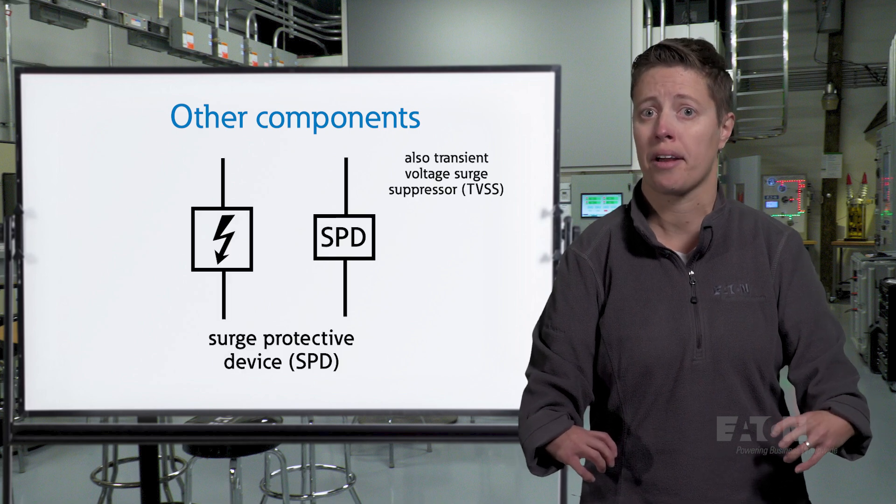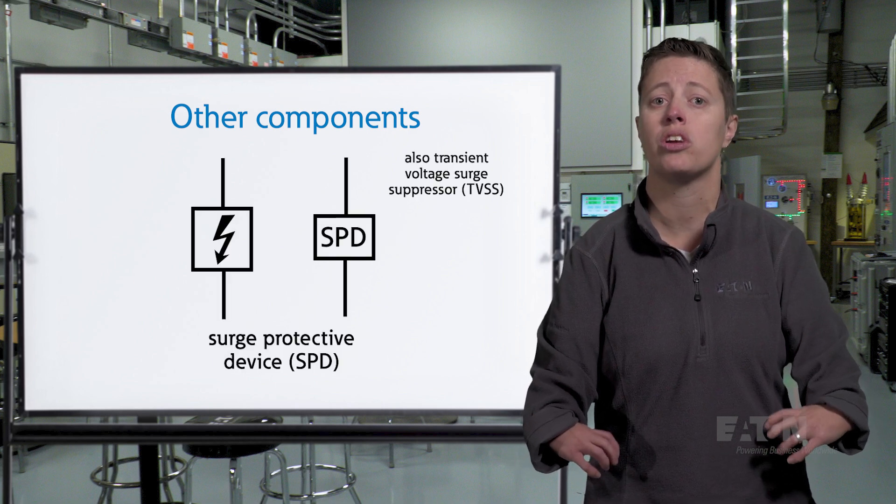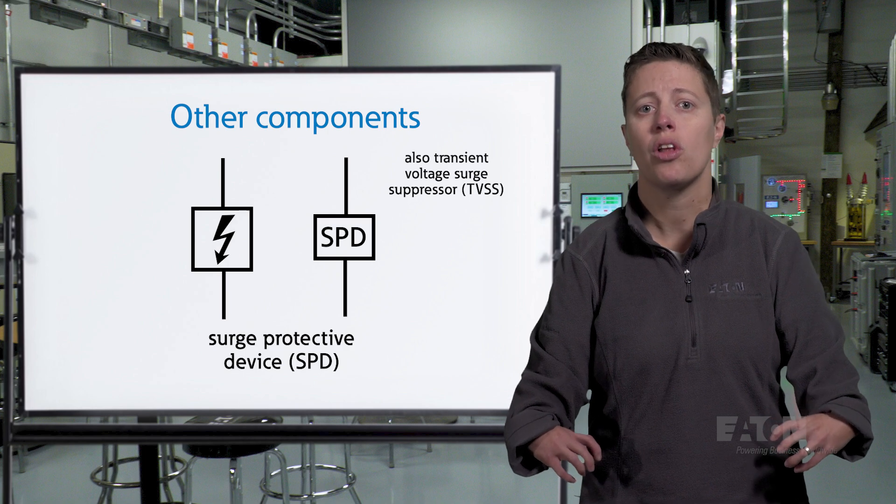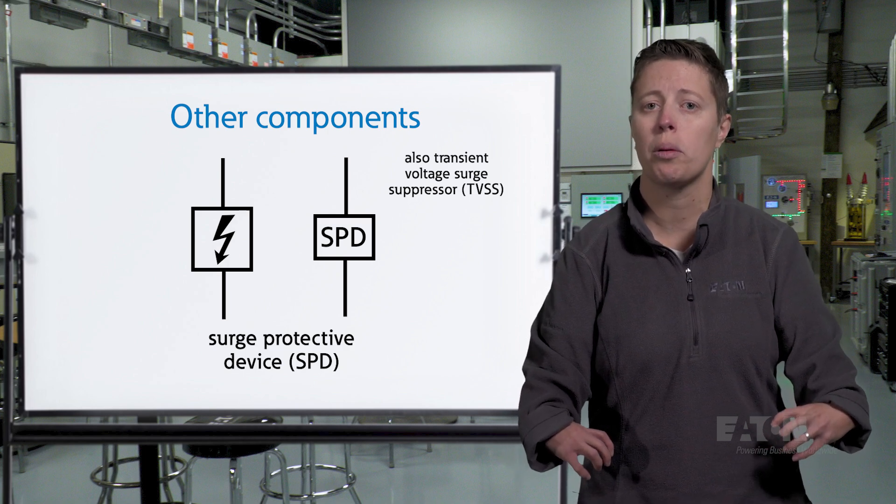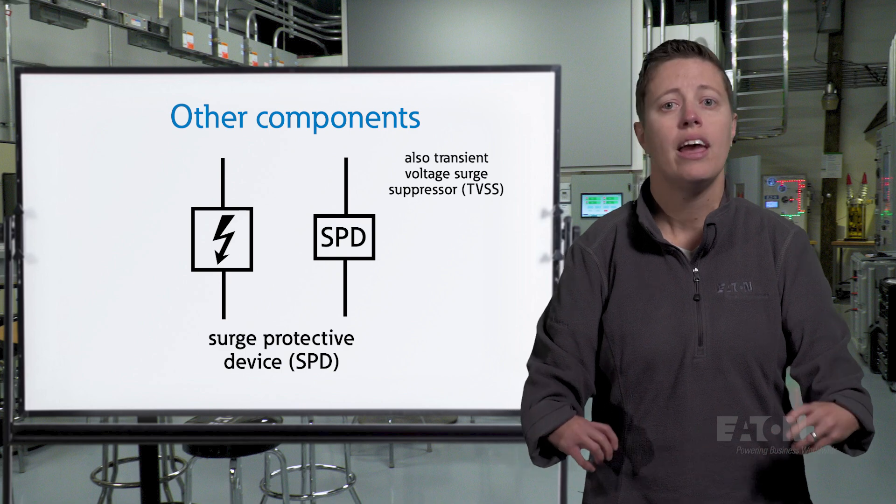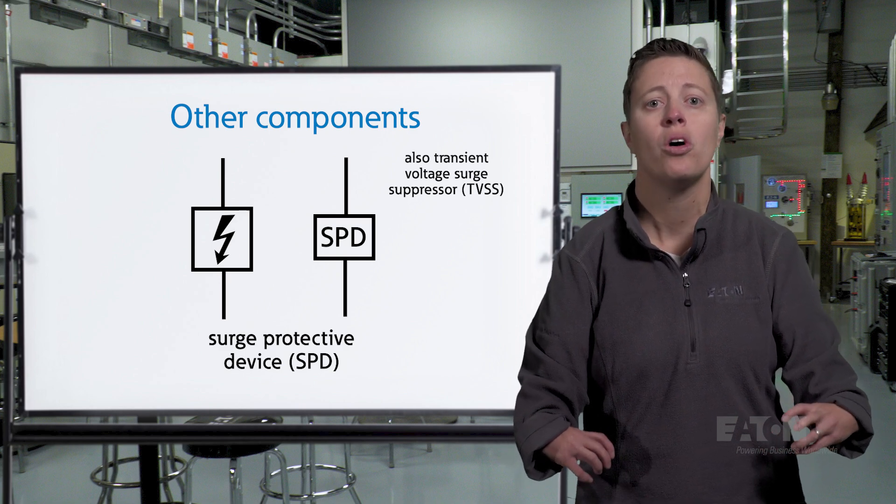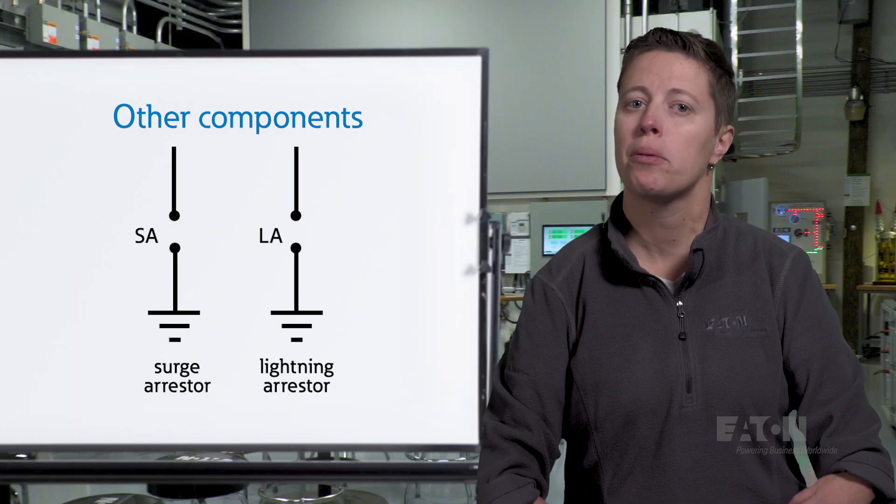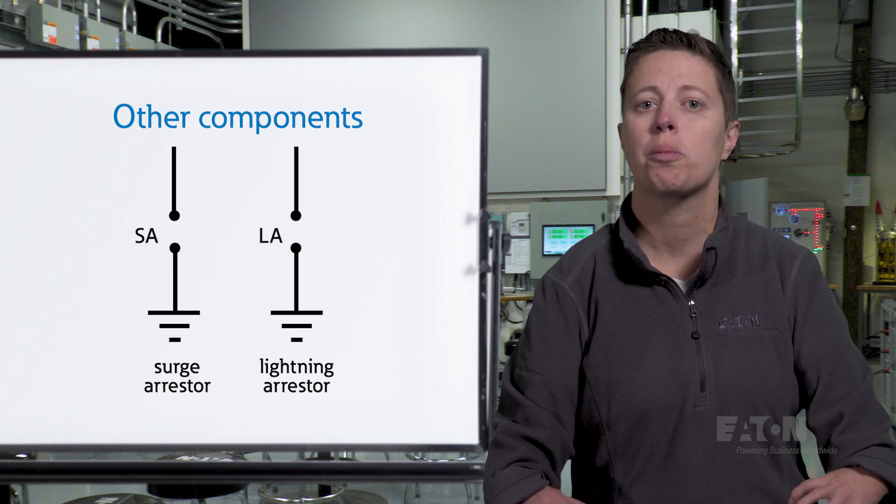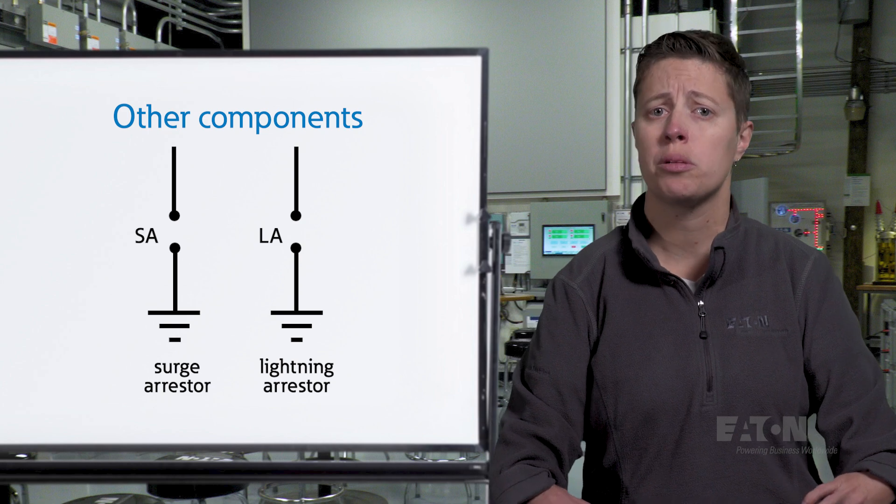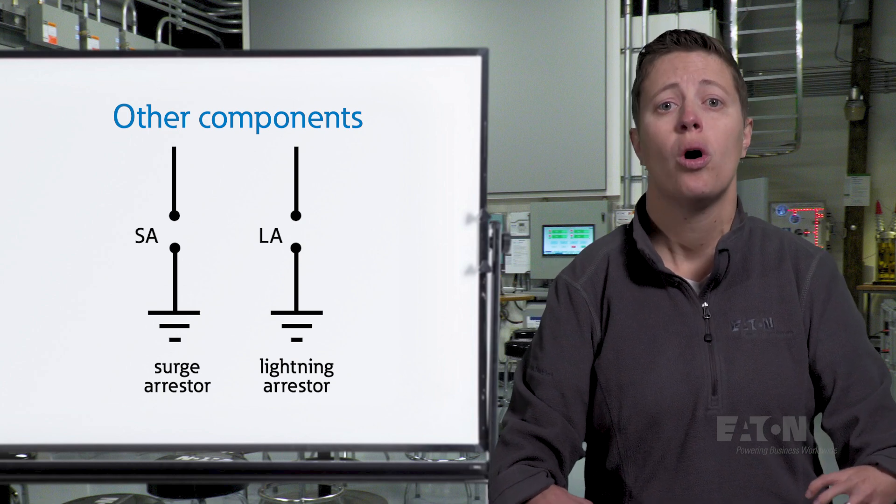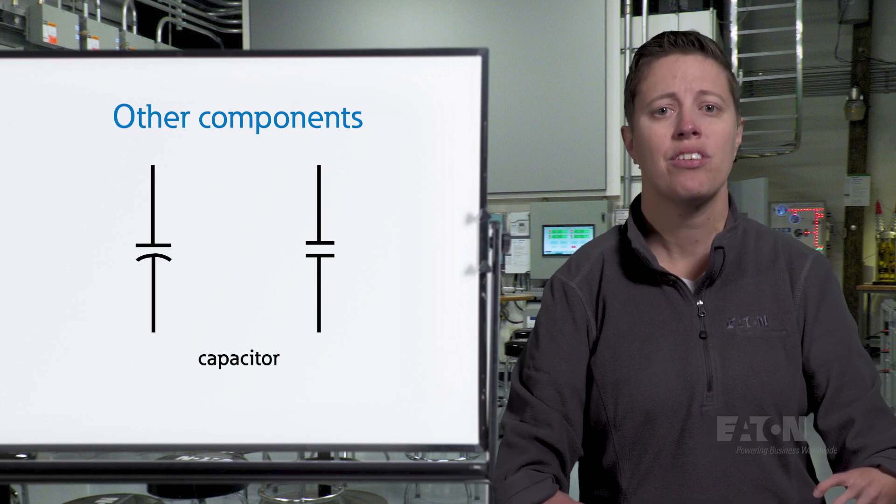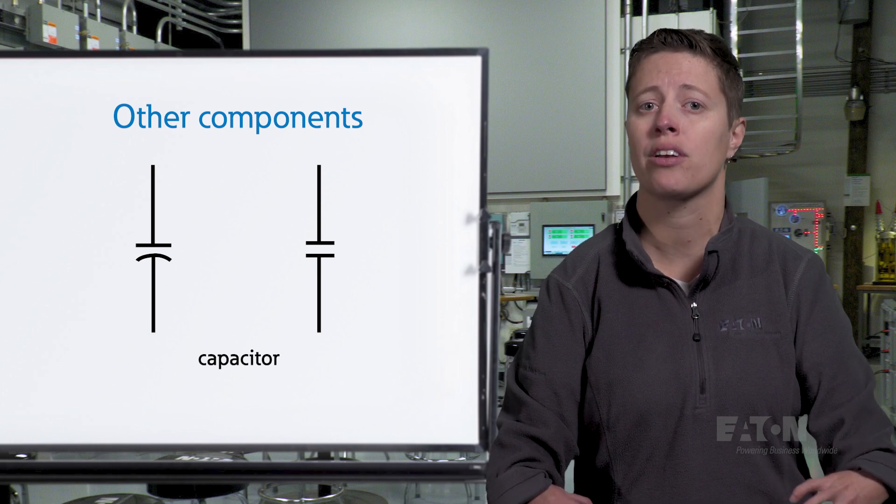A surge protective device, also called a transient voltage surge suppressor, abbreviated SPD or TVSS, represents a low voltage electrical device used to protect equipment from voltage spikes. It is usually depicted as a rectangle with a lightning bolt or the letters SPD inside. A surge arrestor or lightning arrestor symbol represents a medium voltage electrical device used to protect equipment from voltage spikes. It is usually depicted as a lightning bolt symbol or a series of parallel lines with the letters SA or LA.